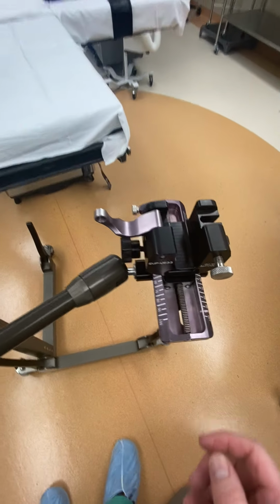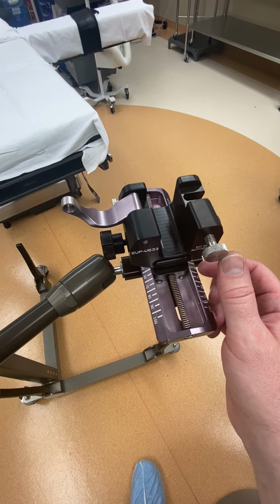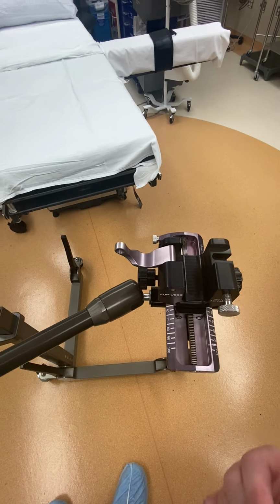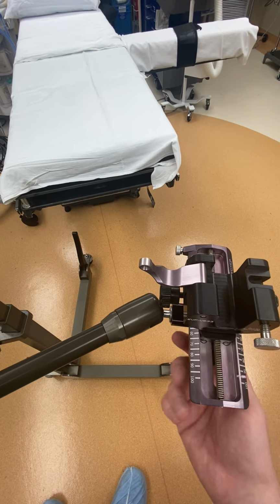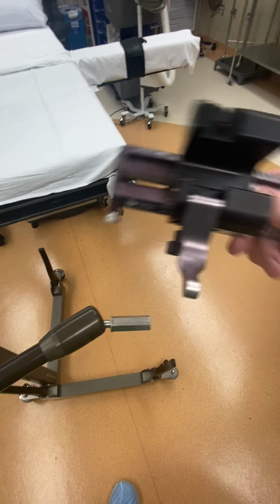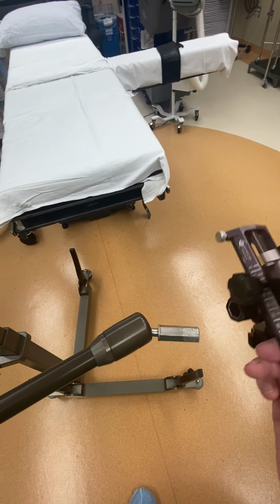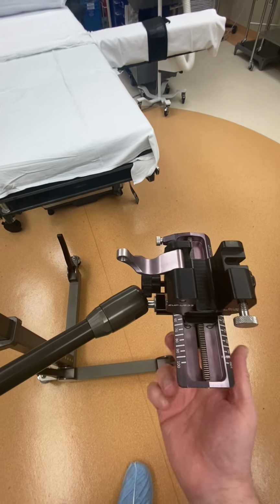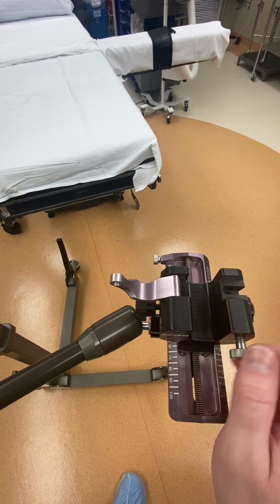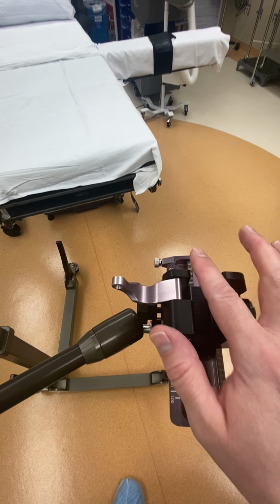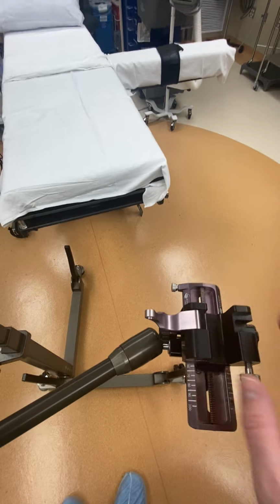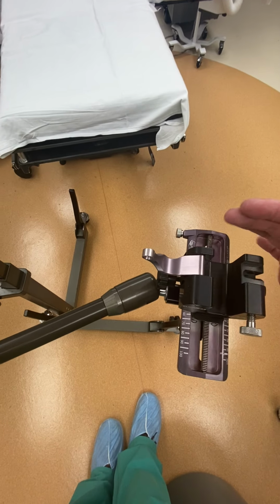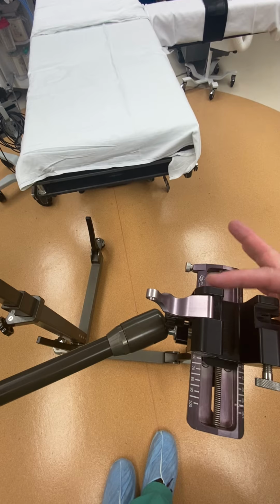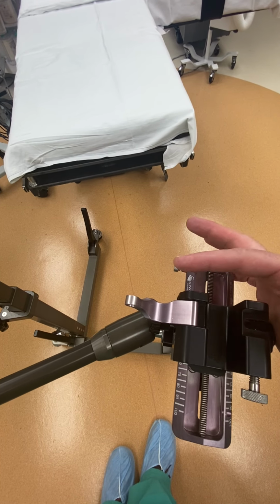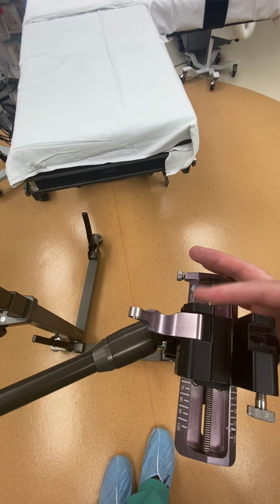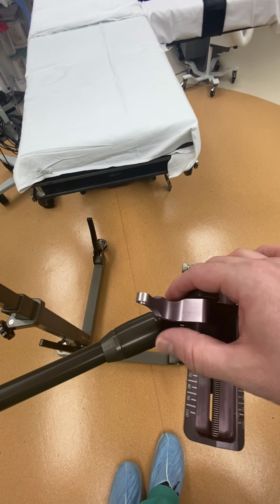You want to make sure the big silver bolt on the cradle is facing the back side, or facing toward you. If it's the other way around, then you have this backwards, because it is possible to put it on both ways. So you want to make sure that that silver bolt is on the back, because then it's a lot easier for the urologist or you to tighten this down when the probe is in the cradle. Basically, the probe will fit into the cradle here, so that the tab that's on the biplane probe is flush against this front side. You'll see there's a little tab sticking out that needs to be flush against the side. If it's too far up or back, it won't lock in properly.